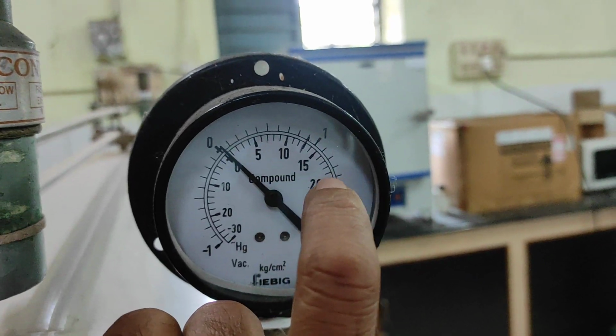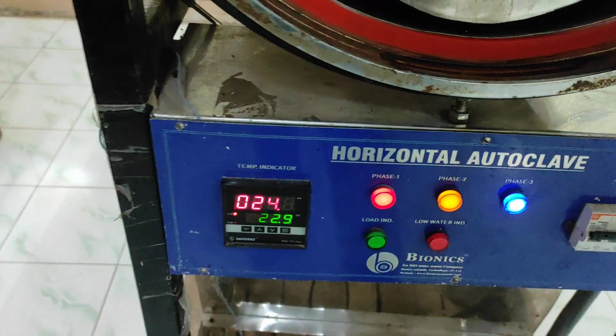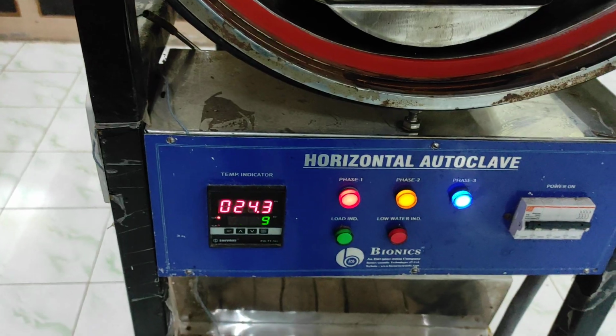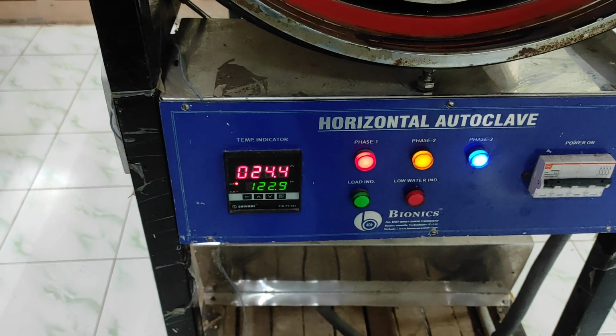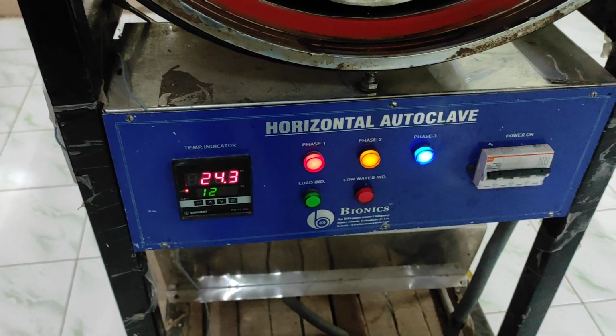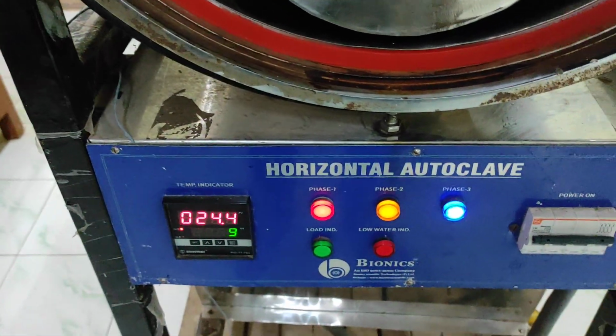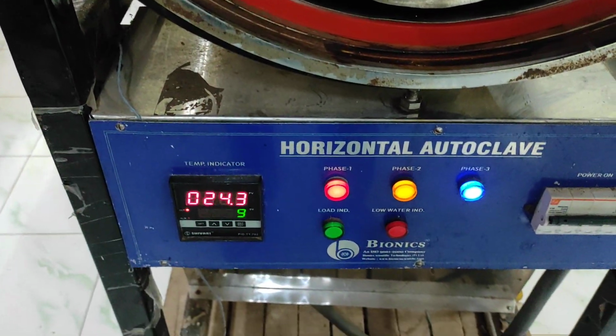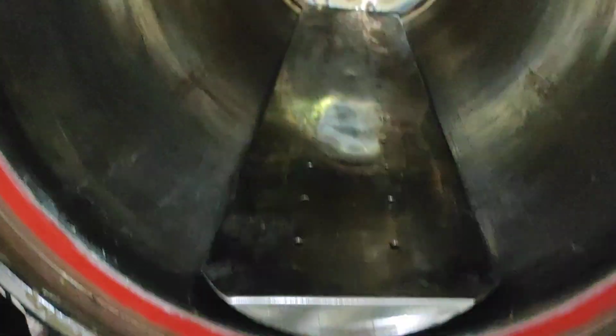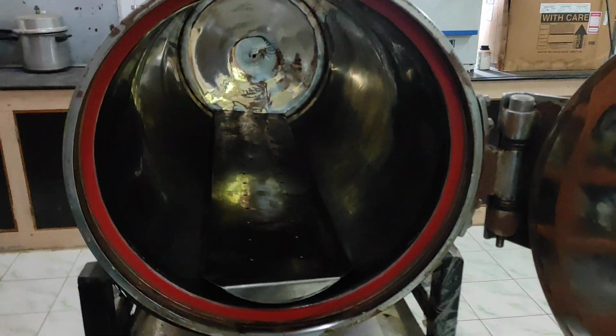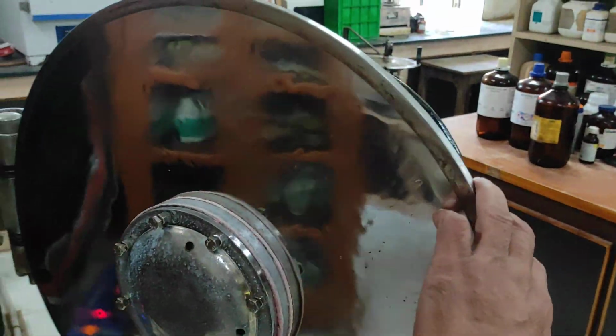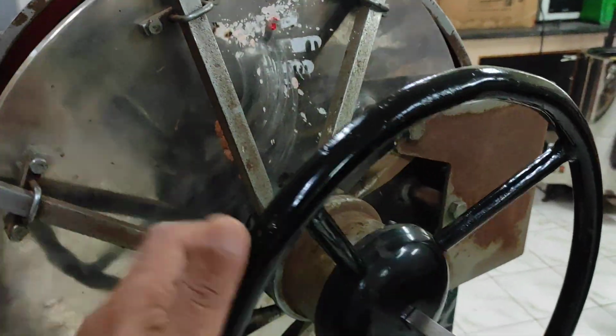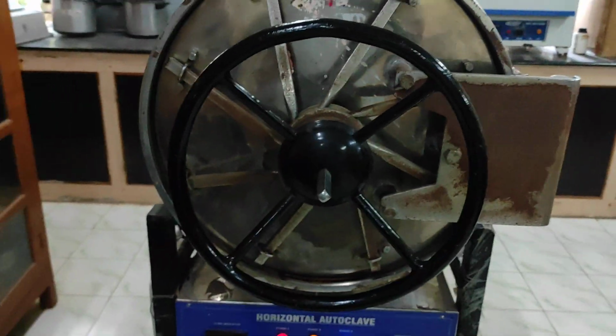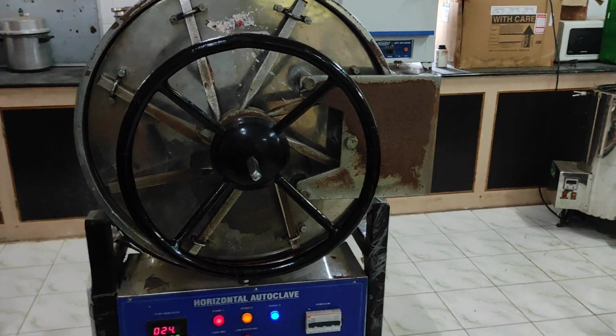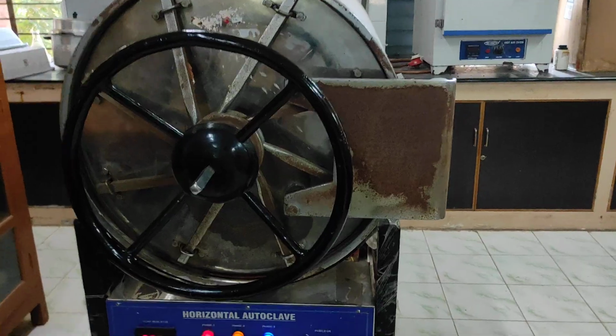When it reaches 15, since it is an automatic system, we have adjusted it for when the temperature is 121 degrees centigrade. And the timer is also adjusted, 15 to 20 minutes or based on our requirement. Then automatically, when the time period is over, it switches off. So this is the sterilization chamber, and this is the heavy duty lid. I think we purchased it around 6-7 years back. Still it is working fantastic.